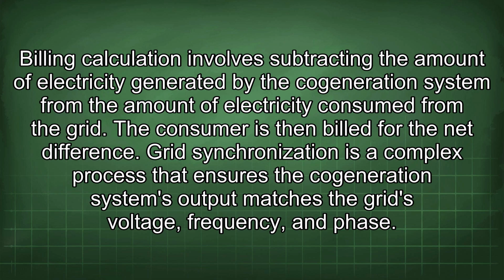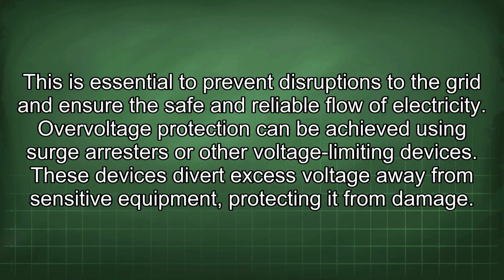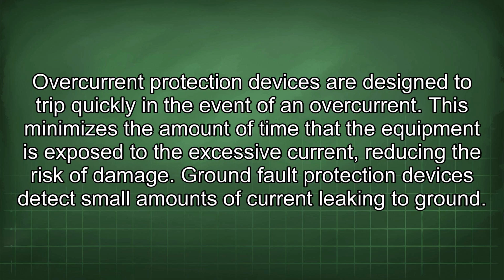Grid synchronization is a complex process that ensures the cogeneration system's output matches the grid's voltage, frequency, and phase. This is essential to prevent disruptions to the grid and ensure the safe and reliable flow of electricity. Overvoltage protection can be achieved using surge arresters or other voltage-limiting devices. These devices divert excess voltage away from sensitive equipment, protecting it from damage. Overcurrent protection devices are designed to trip quickly in the event of an overcurrent.